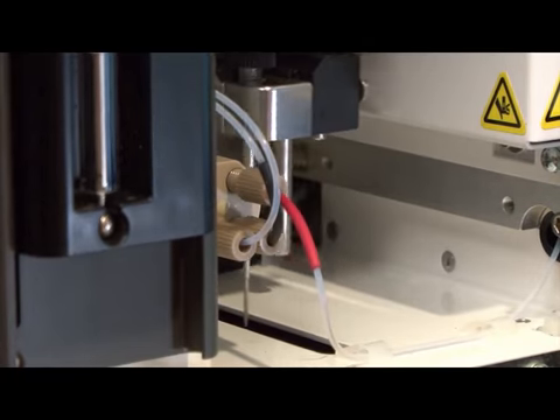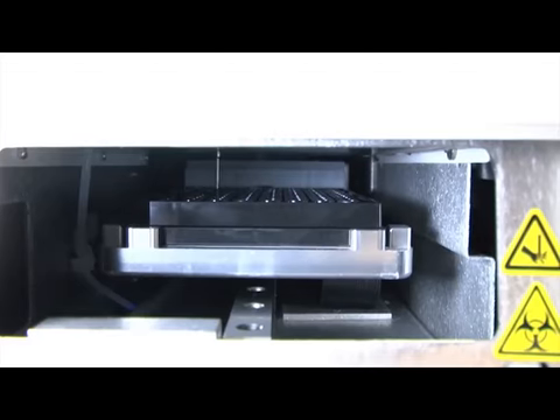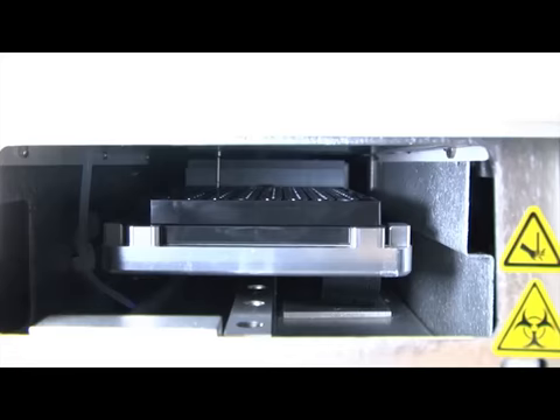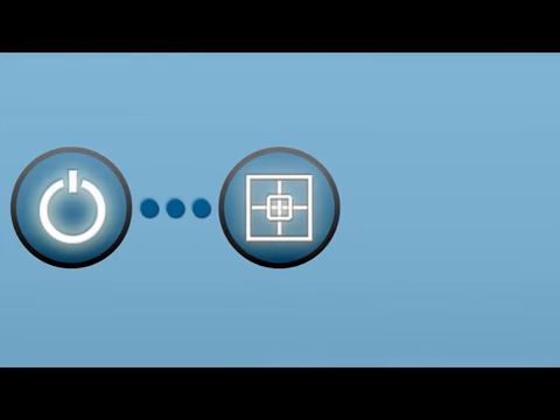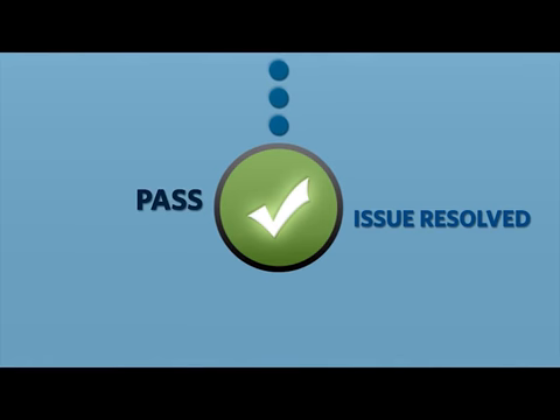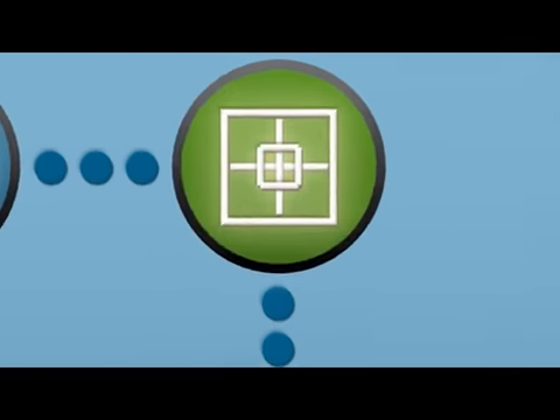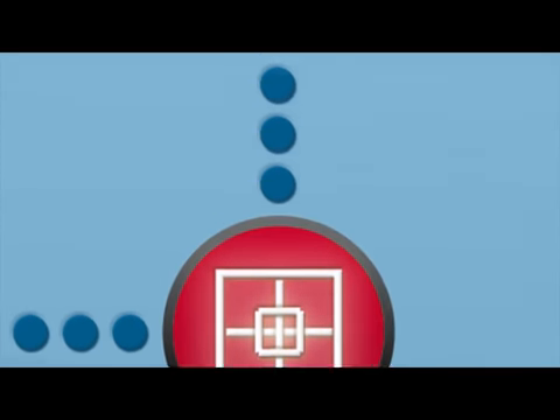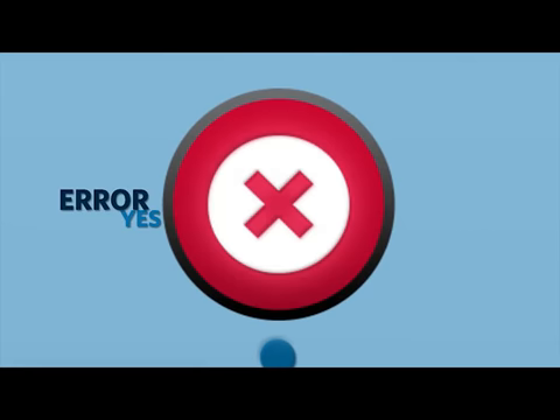The instrument goes through all the same functions as when running an assay, with the added bonus of ensuring optimal and consistent microsphere classification, as well as a properly functioning analyzer when you are done. If the calibration and verification cycle completes with no errors, the hardware for the MagPix instrument is working properly. If your assays are still reporting abnormal readings after this step, review the assay instructions carefully.